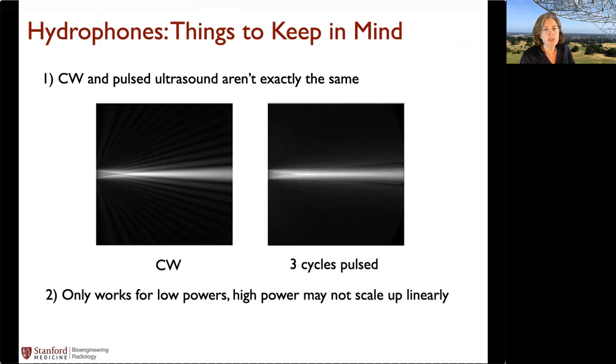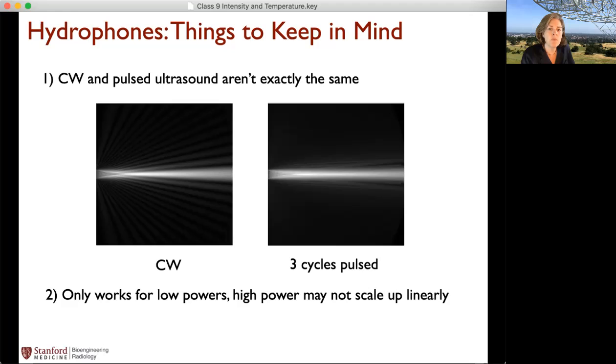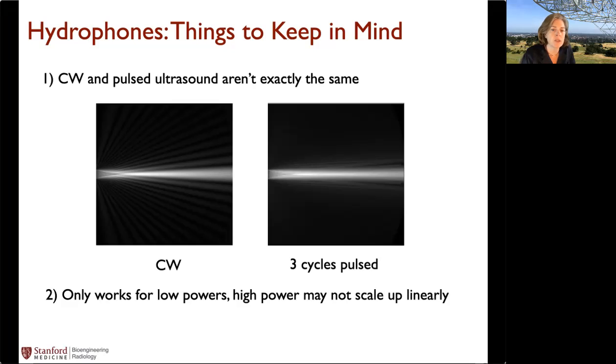All right, so a couple of things to keep in mind for hydrophones. One of the things is that CW and pulsed ultrasound aren't exactly the same. So if you're thinking about doing your neuromodulation in CW, and that's anytime you have more than a few cycles, maybe more than 10 or 20 cycles, and it sort of becomes a CW, then the beam pattern actually is a bit different.